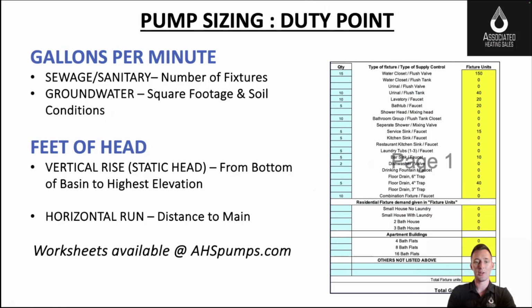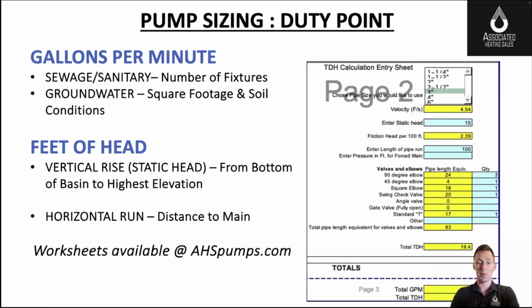And then the second consideration is how many feet of head you're pumping against. In pumps, it's feet. So most of the feet of head you're pumping against is the total vertical rise in your system. So where the pump's located up to the highest point in the pump line, that's your vertical component. You do add a horizontal component. It's very little if you're in an appropriate size pipe, is what I should say. So when you go from 2-inch to 3-inch, the 3-inch line really does not have a lot of friction or horizontal head that we're adding to it.